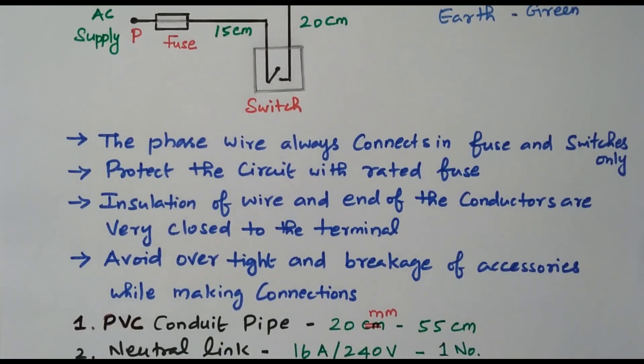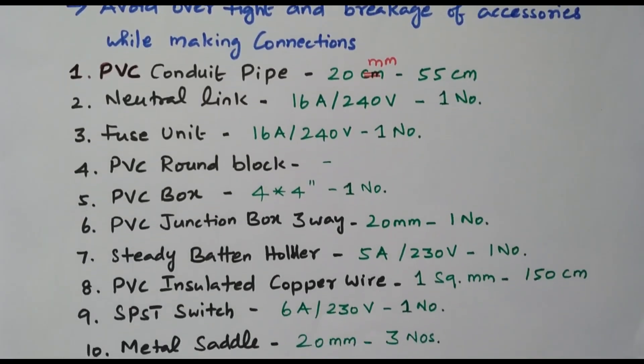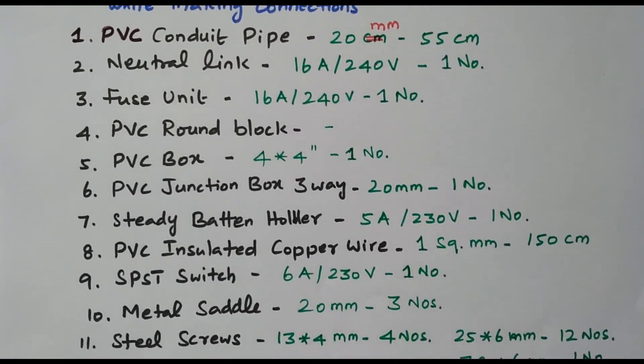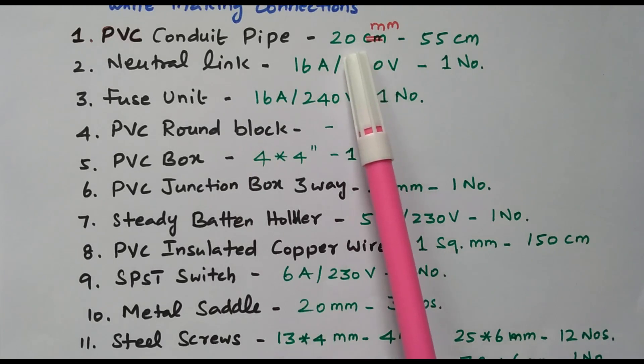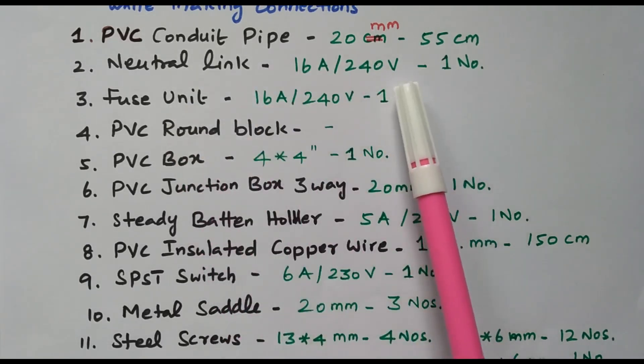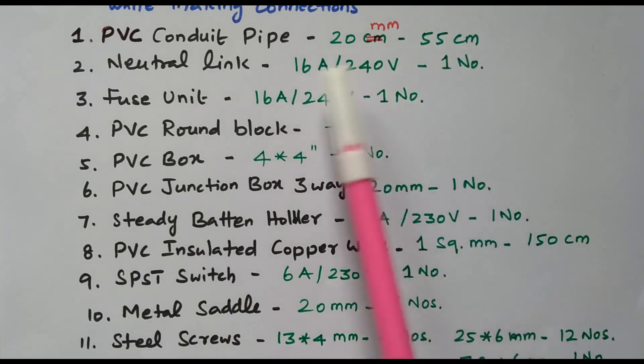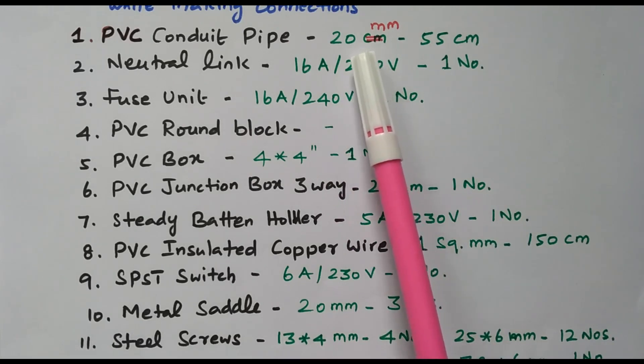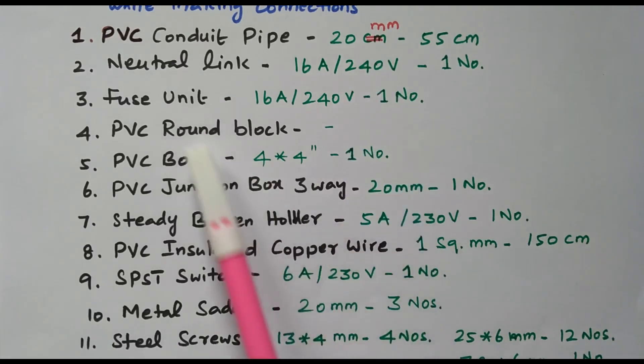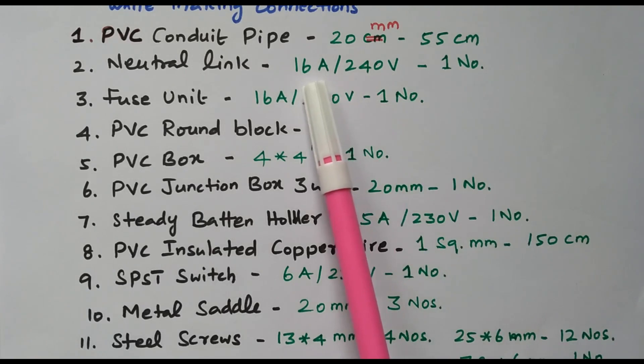Now we will see the materials required for wiring one bulb controlled by one switch. PVC conduit pipe, 20 mm diameter, 55 centimeters required. Neutral link, 16-ampere, 240-volt, one number required. Fuse unit, 16-ampere, 240-volt, one number required.